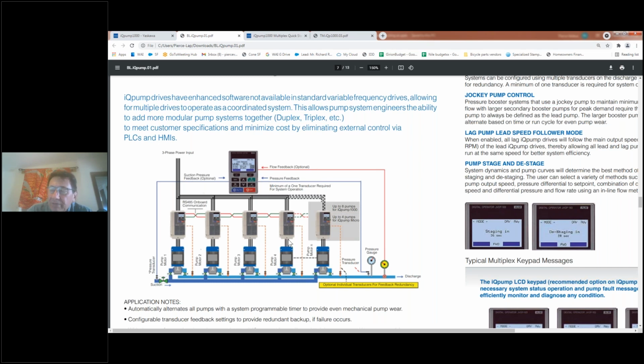And then there's an additional benefit in that the master can be designated to change per schedule, not because of a failure, but just per schedule on any given day. So if this is Monday, Tuesday, Wednesday, Thursday, Friday, Saturday, Sunday, Monday, you can keep circulating the masters. What does that do? Well, it evens out all the wear on the pumps. Your wear rings won't fail prematurely, well, they may fail prematurely for some other reason, but they're not going to fail because of wear, because we're evening out the runtime on all of the pumps as well. And that's a significant benefit towards obtaining maximum life of the system.